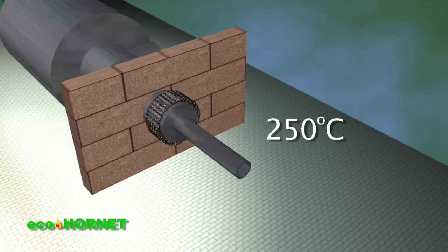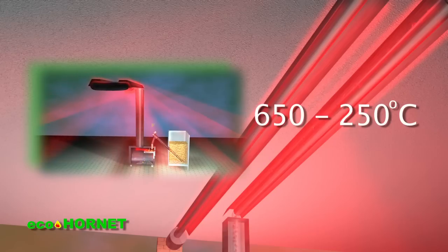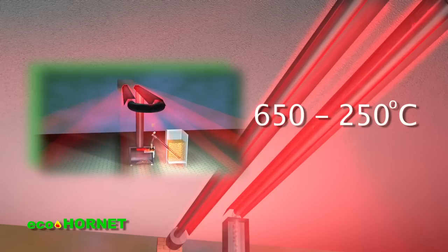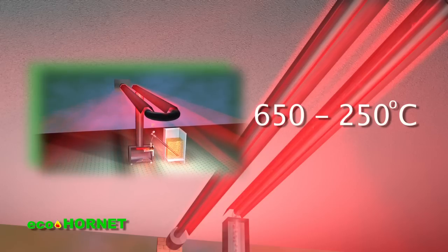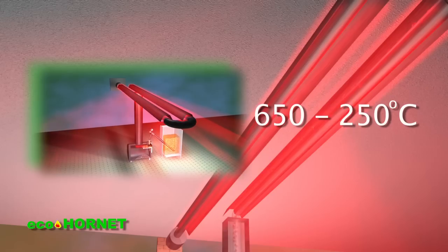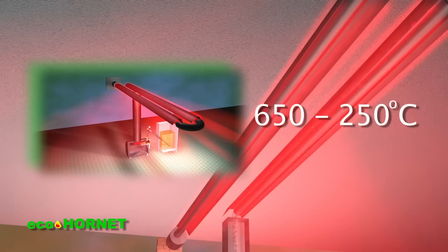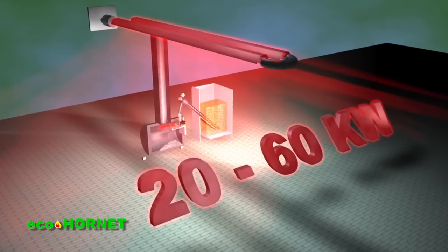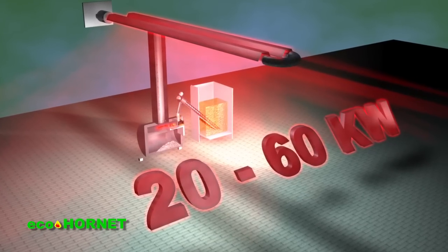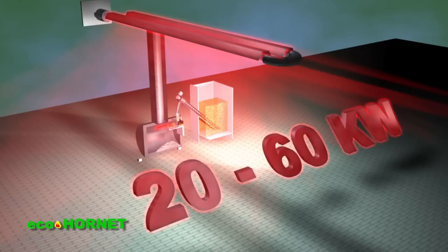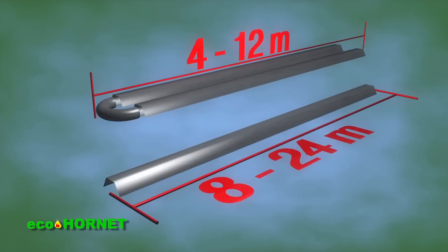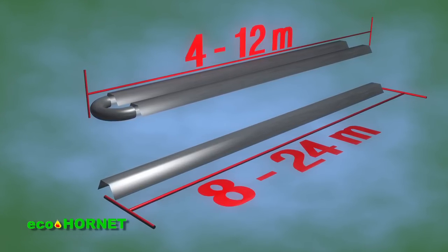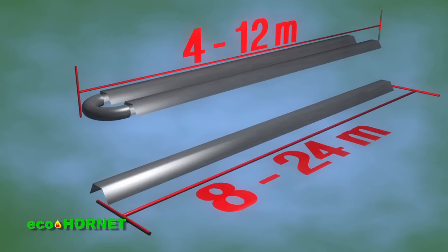The distribution of temperatures in the radiant tube between 650 and 250 degrees Celsius ensures the uniform heating of the space by infrared radiation sent to the ground by the projector located above the heated tubes. The power of the radiant tube burners ranges between 20 and 60 kilowatts with U-shaped linear tubes with a length of 4 to 12 meters or with linear tubes with total lengths between 8 and 24 meters.